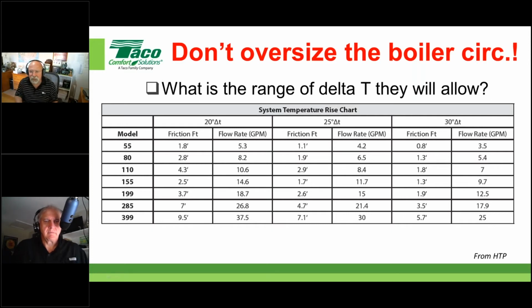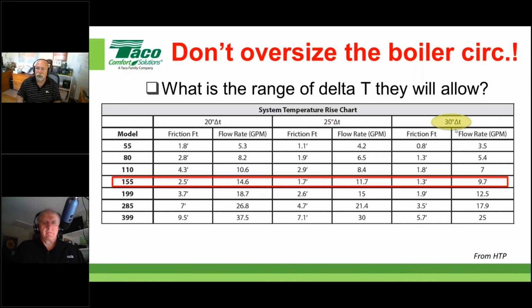In this case, I have one from HTP, and I'm going to focus on a 150,000 BTU size all across the board. I think I'm going to show you four manufacturers, with the same information. Notice they say you can do a 20, here's what it would be at a 25, here's what it would be at a 30. By all means, my push to you is to take it out as far as they'll let you. You'll see why as we go.